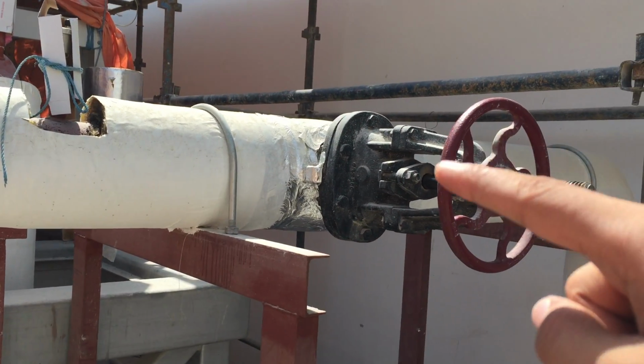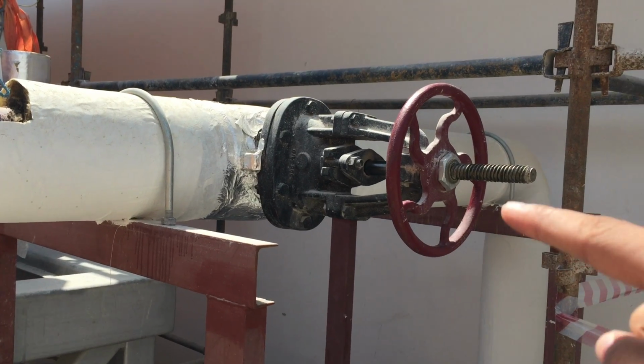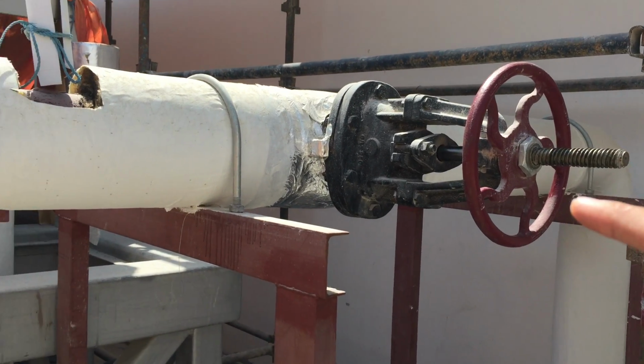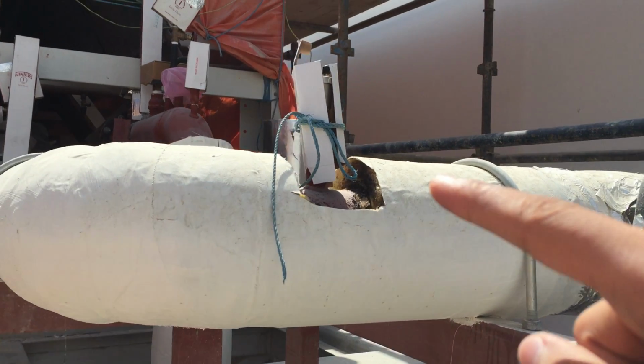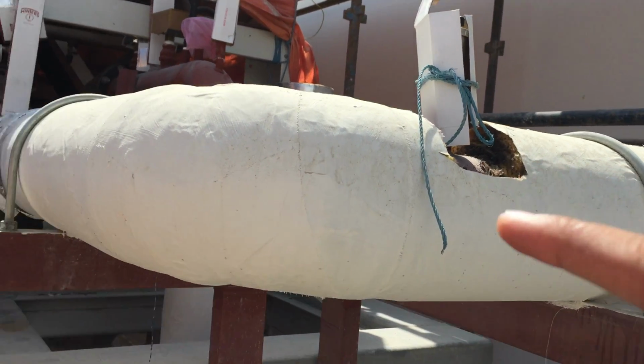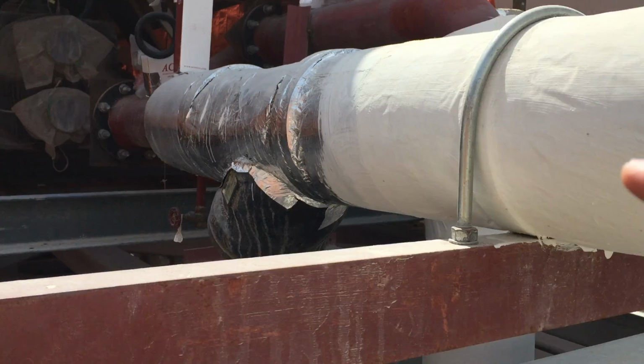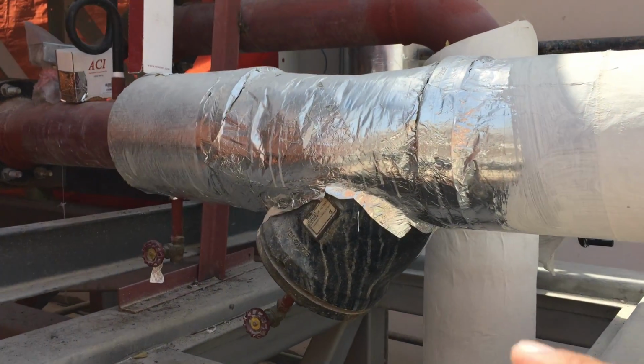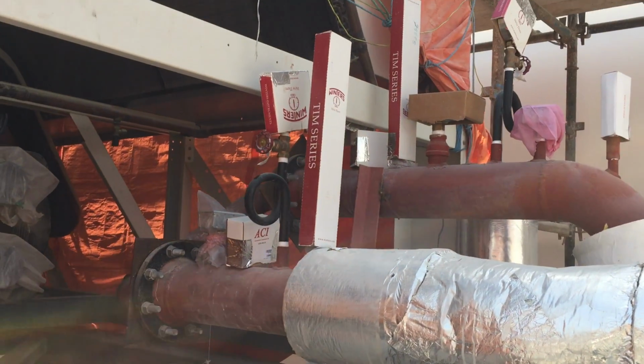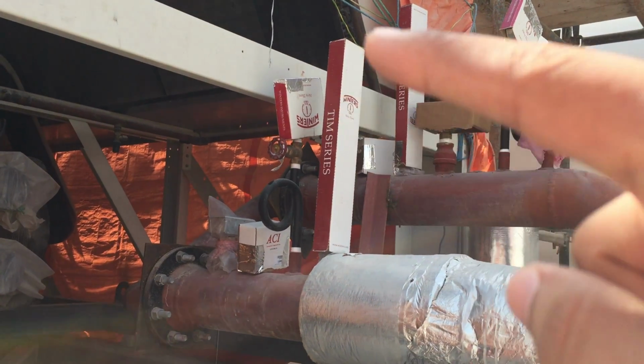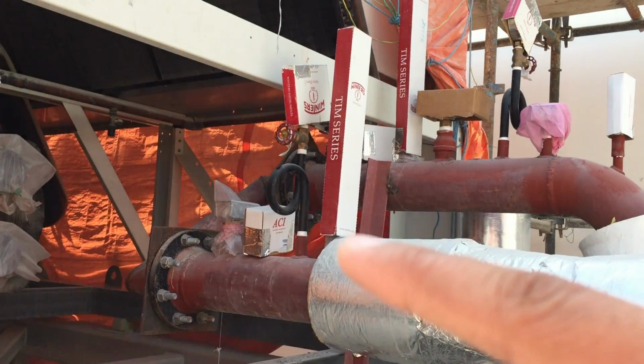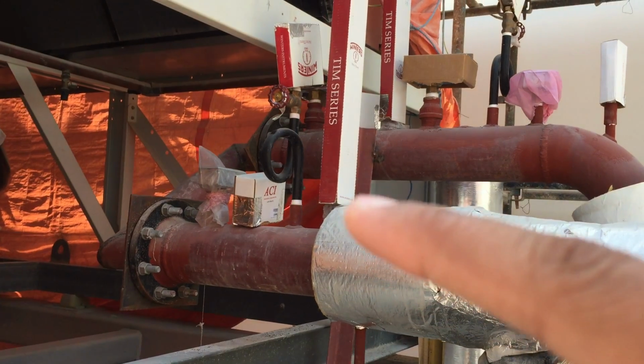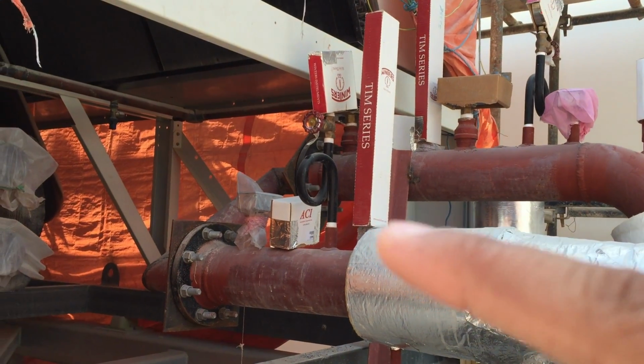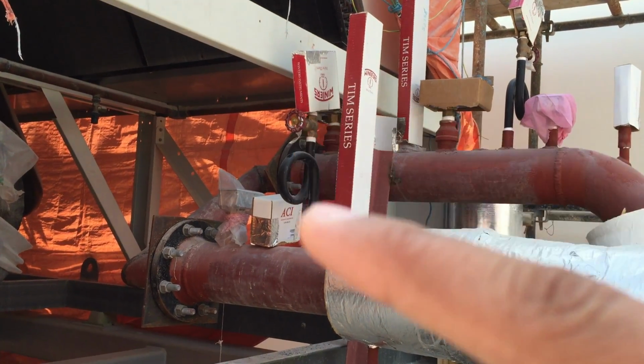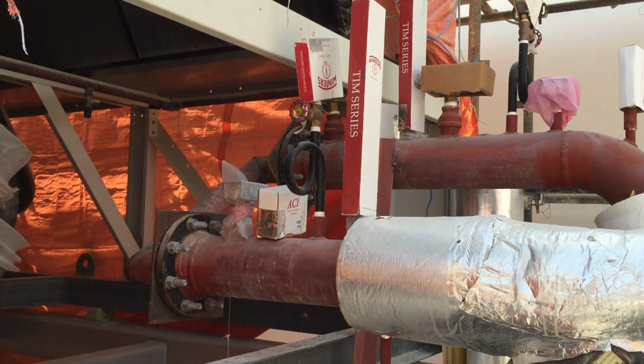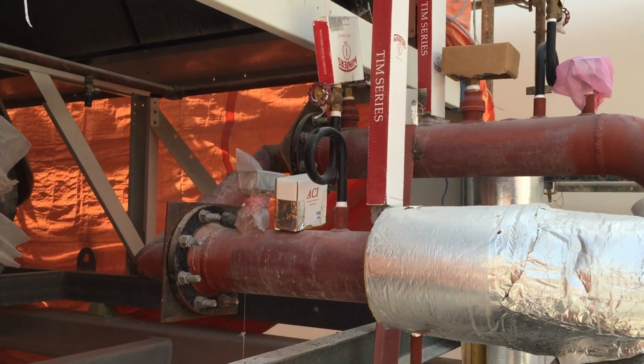You can see this line here, this is coming from primary chilled water pumps. First of all, we use here this isolation valve. Right now we are using OS&Y gate valve for isolation. Second one here is air vent. Third we have here strainer. Then we have this thermometer, just to know what is the current temperature in the inlet line for chiller. Second one is pressure gauge, to know what is the current pressure in the inlet line for chiller.